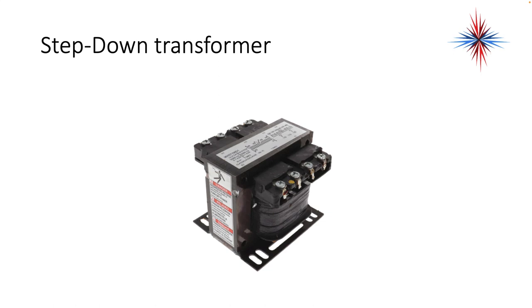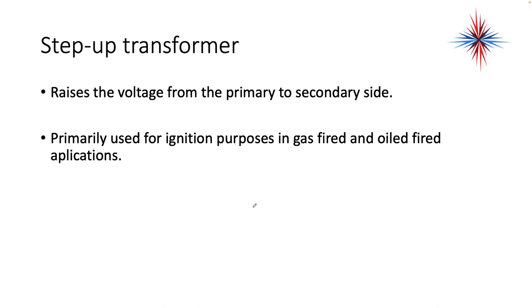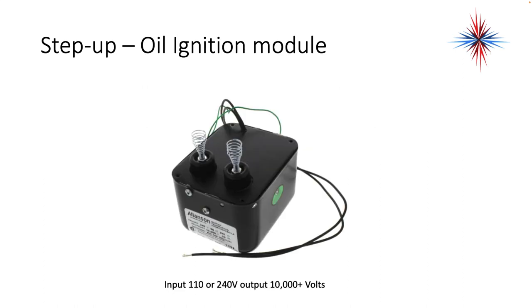This is an example of a step-down transformer with multiple taps on each side. Step-up transformers raise the voltage from the primary to the secondary side, primarily used for ignition purposes in gas-fired and oil-fired applications. This is an example of a step-up oil ignition module. My two black wires are going to be 120 volts or 240 volts depending on the system and the label. My output is these two springs here that connect to the igniters — this is going to be a 10,000-volt output, and some are going up as high as 14,000 and 16,000 volts. Very little amperage, but it's enough to give you a real jolt. Do not put your meter on these outputs to measure voltage — there are other ways to do it.